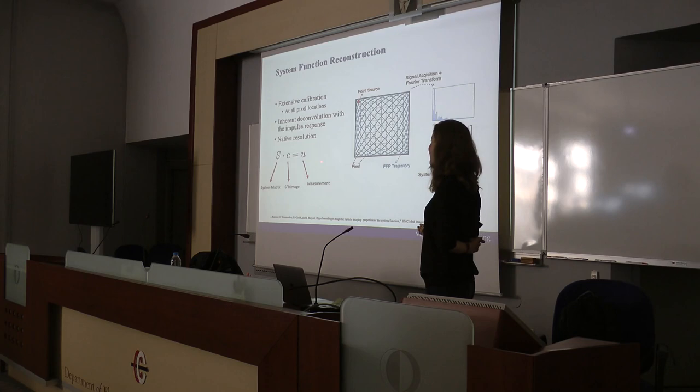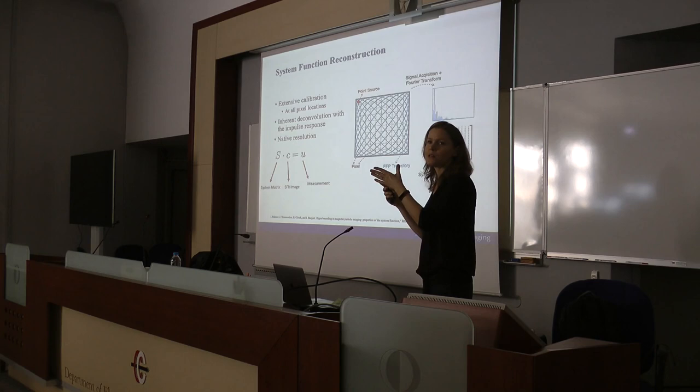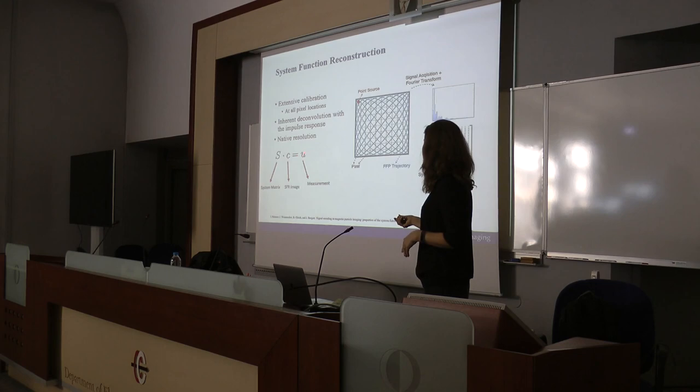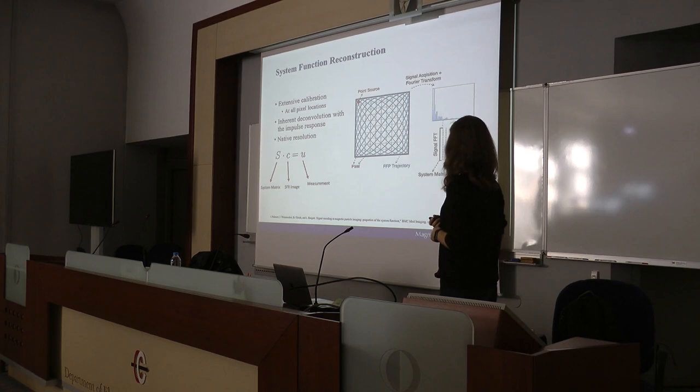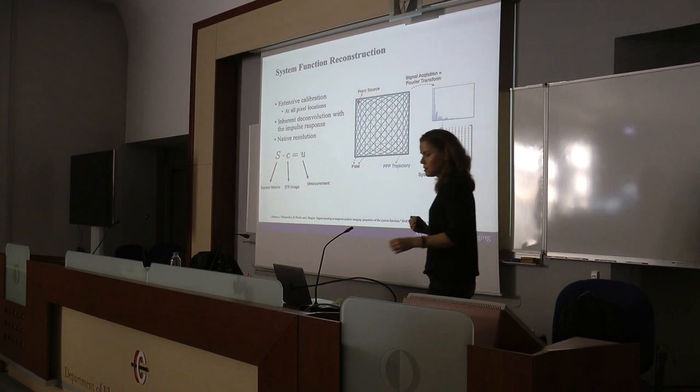For imaging, the object of interest is placed in the field of view, the same trajectory is run, the signal is recorded as vector U, and an inverse problem is solved to determine at which locations the nanoparticles were. The problem with this procedure is the length of calibration — it currently takes around 24 hours to perform this calibration on an MPI scanner.